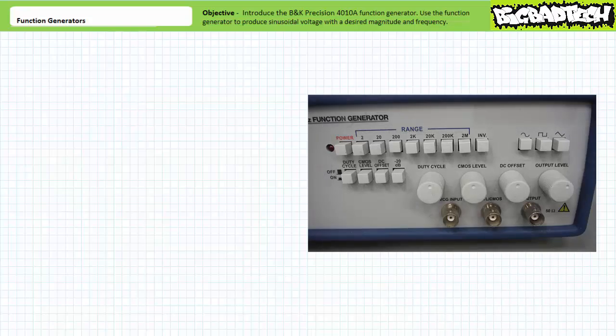Let's start with the most obvious setting first. Looks like the BK Precision 4010A function generator is capable of producing three styles of waveforms: sinusoidal, square wave, and triangle. Select sinusoidal. Several selector buttons modify the output for special-purpose scenarios. Examples would be duty cycle modification or whether or not we wish to include a DC offset. We don't want any of these modifications today, so ensure all these options are off.